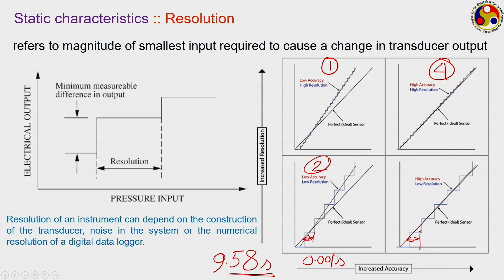That is the smallest possible value it should be measured with small change, and preferably up to a third decimal, because there are several situations where you may have to go for a photo finish, and there even 2 decimal points may not be sufficient. We may have to measure even the third decimal point also. So, there we need an instrument with such kind of resolution, but not always. That depends upon application, and accordingly you have to choose the resolution of the instruments. So, resolution and sensitivity probably are the 2 most important static characteristics a system should have.